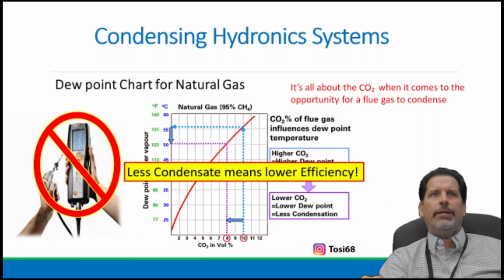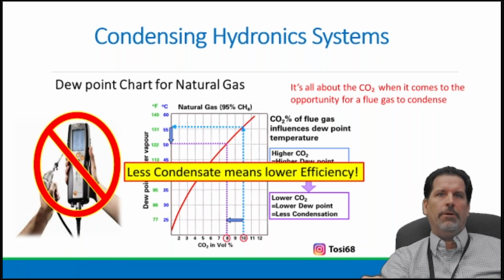Please use a calibrated combustion analyzer too. It's a tool, it's an instrument, right? It tells us a lot about what's happening inside our flue gases. And now we have the ability to set it up, document it, print it, and leave it with the homeowner. This is a liability thing as far as what you do at the time of leaving your job sites.